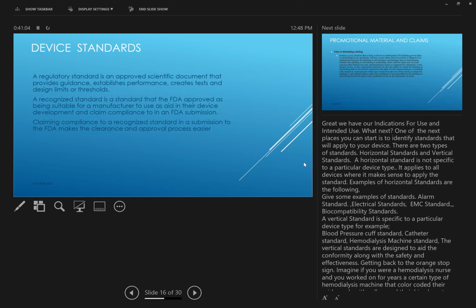So getting back to the temperature and accuracy example, there are accuracy standards for temperature and thermometers. As part of that device standard, they'll give you a test method for how to go about the test, and then the accuracy requirements. As part of your validation and verification testing, you show the FDA that you looked at the standard, performed the test according to the standard, and here are your test results. By claiming compliance to a recognized standard in a submission, the FDA knows the device meets that standard. Again, it gives them some assurance that the device is going to be safe and effective. If you meet the temperature threshold and the accuracy of that standard, they know, and I keep repeating it, but it's very critical, that the device is actually intended to be a thermometer and is accurate as a thermometer.